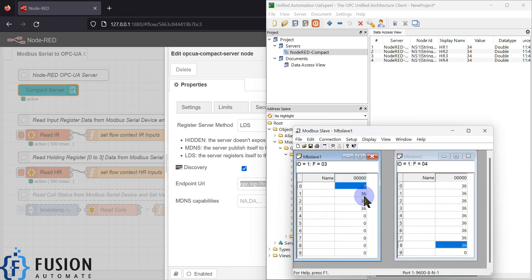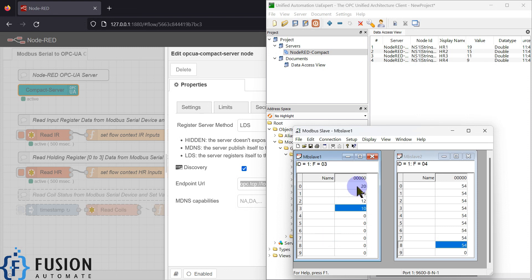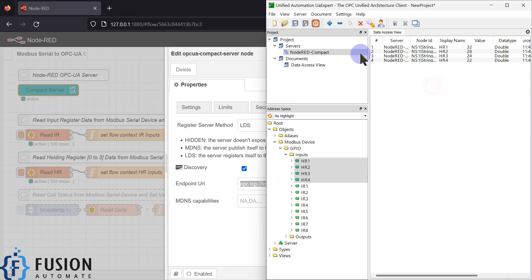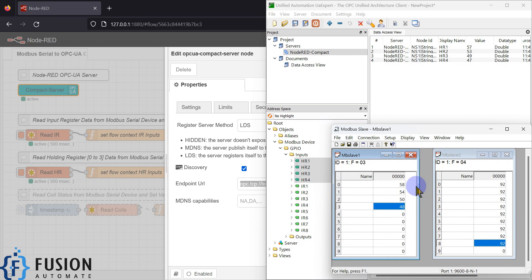Now you can see the values are starting to update. Whatever value you are seeing in the Modbus slave software, the same value is populating or publishing to the OPC UA server, and with the OPC UA client I can read those values. This is how you can convert your Modbus serial data into OPC UA data.